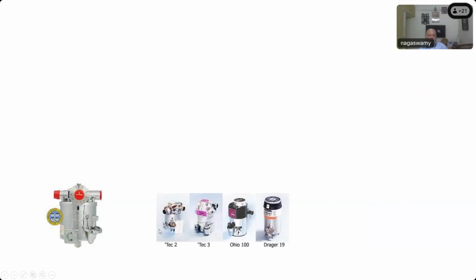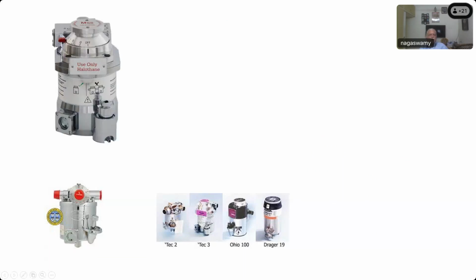So the word Tec stands for temperature compensation. That is how this word Tec was introduced. So all these vaporizers are temperature compensated. Then you had Tec 1, Tec 2, Tec 3, Tec 4, up to Tec 6 we have. And then Ohio introduced their own without the name Tec. And there you can see this specificity is also written. You use it only for halothane, not for other things.